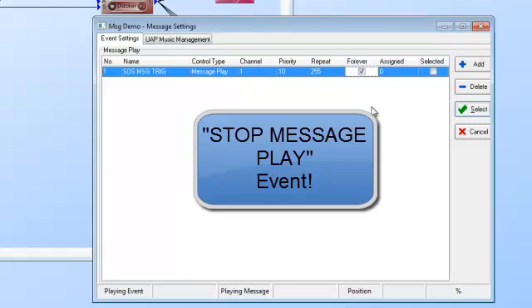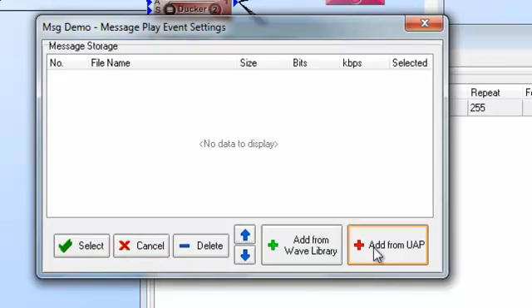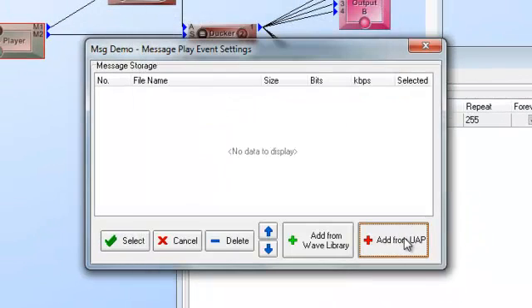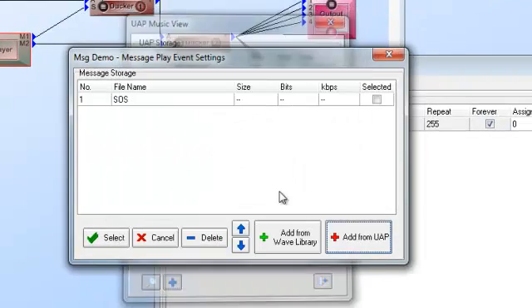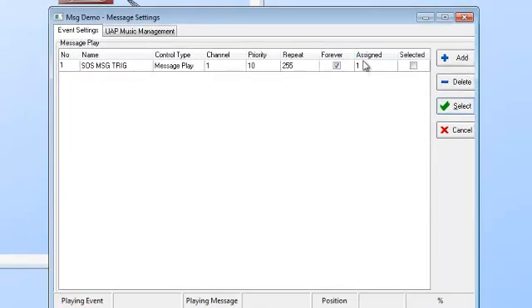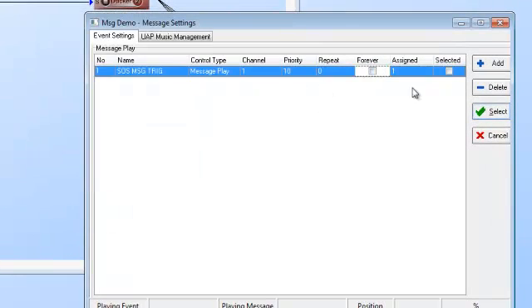I'll show you how to set up that stop event in a moment. The 'assigned' field is where you assign the message to be played when this event is triggered. We haven't yet said how this event will be triggered — we're just naming it and defining what happens. I'll search on my UAP for the SOS file and add it. Now event number one, SOS, is ready to go. If I just wanted this to repeat once, that's all I'd need to do. But for a fire alarm message that repeats until the alarm is cleared, I'll set it to forever.